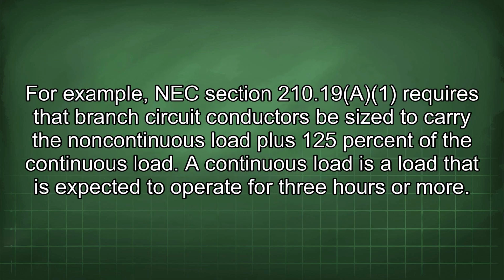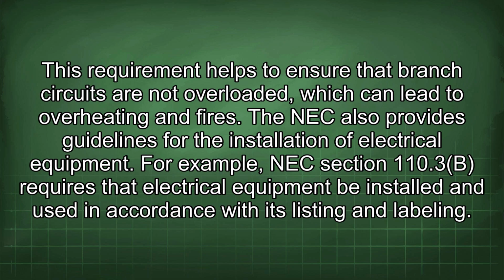For example, NEC section 210.19(A) requires that branch circuit conductors be sized to carry the non-continuous load plus 125% of the continuous load. A continuous load is a load that is expected to operate for 3 hours or more. This requirement helps to ensure that branch circuits are not overloaded, which can lead to overheating and fires.